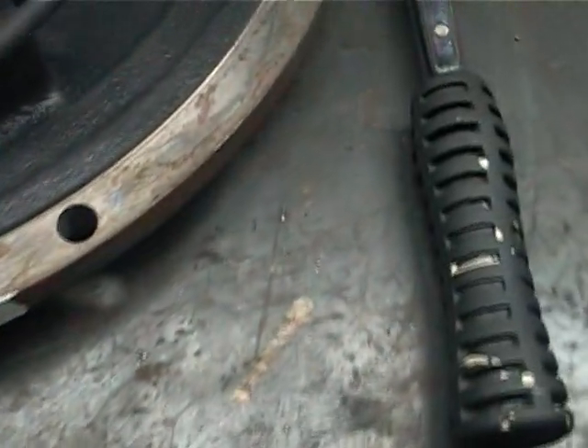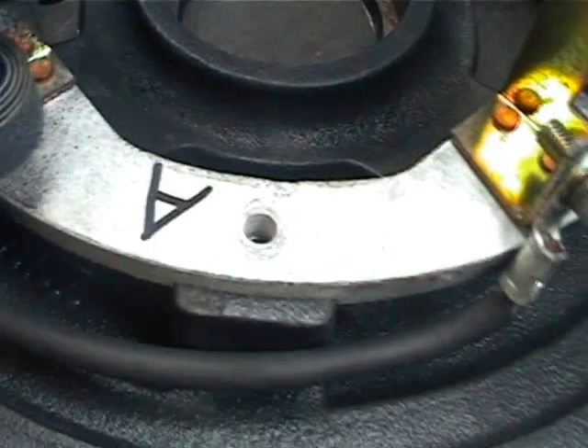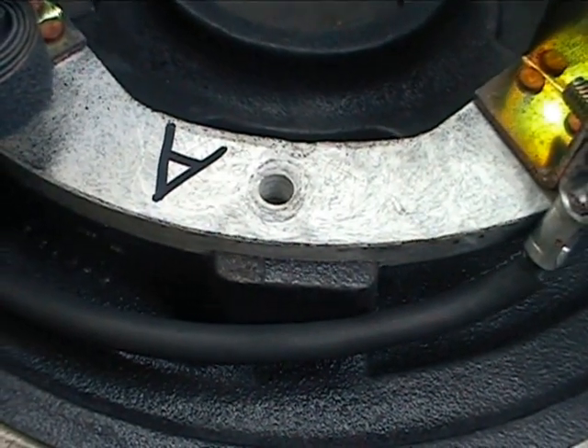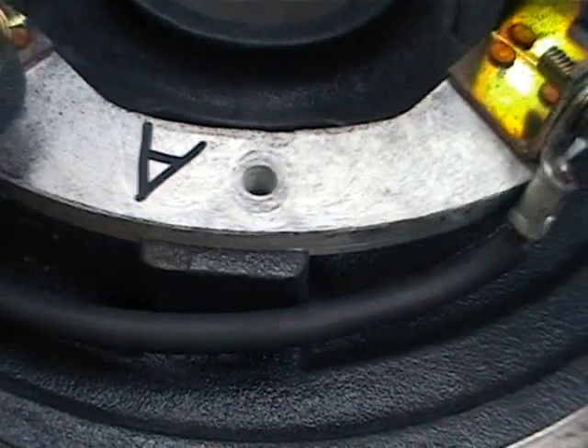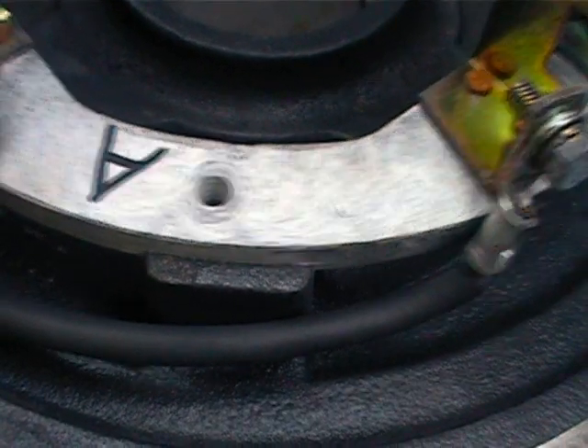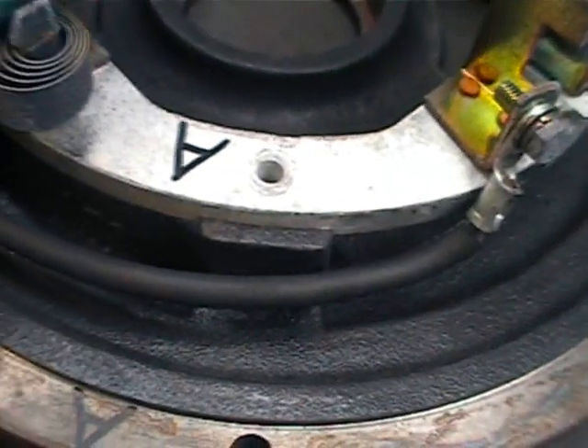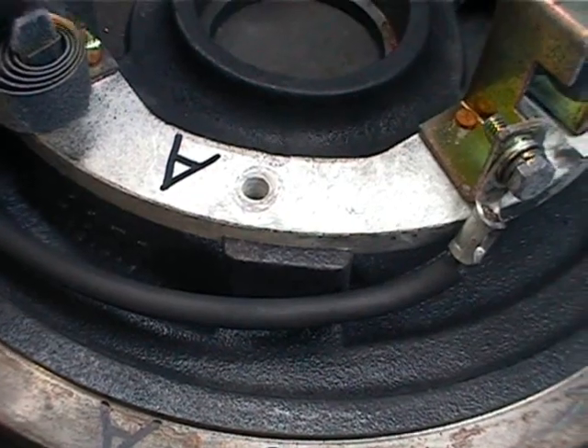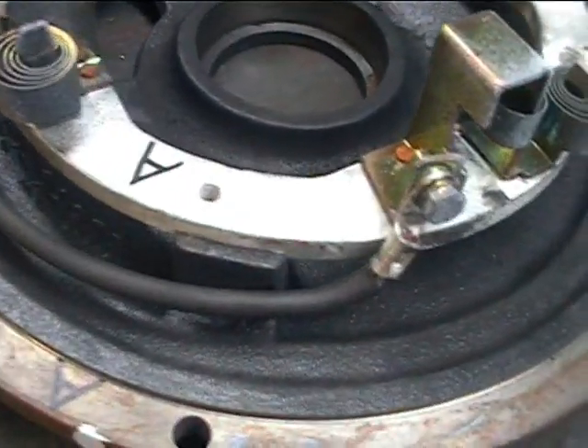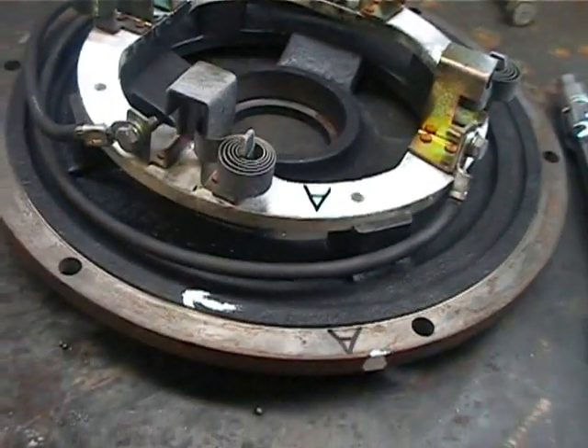The plan now is this: there's our A and our A there. The idea is that we want to move the brush plate this way by a pre-described amount. That's it at zero there. We want to go about that much — generally it's said about 8 to 12 degrees, that's about what I hear.